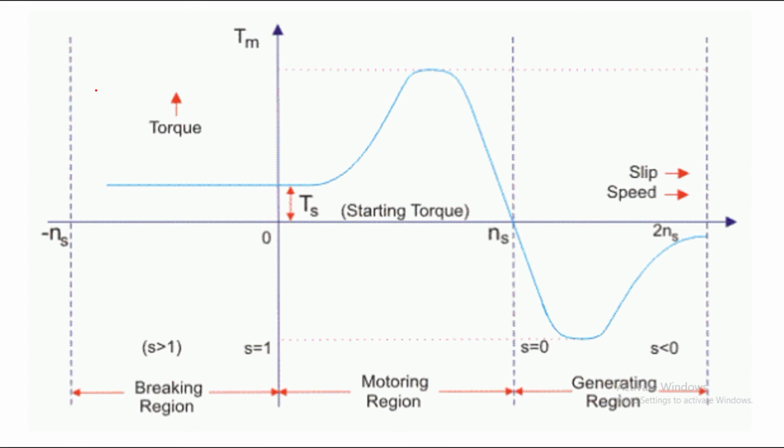In electrical braking we have three types, and here we are going to use the plugging operation. Plugging means it deals with the supply. We all know that we have a phase sequence of R, Y, B in a three-phase AC network, and for that we have a direction of rotation and stator flux in the clockwise direction with the speed of ns. Now for applying electrical braking, that is for the plugging operation, we reverse the phase sequence in the supply connected to the stator winding.